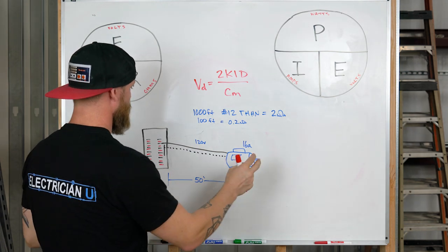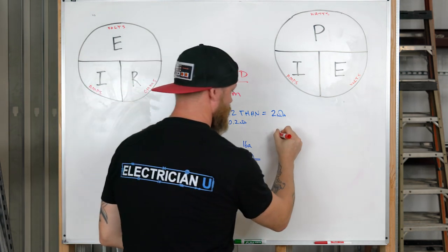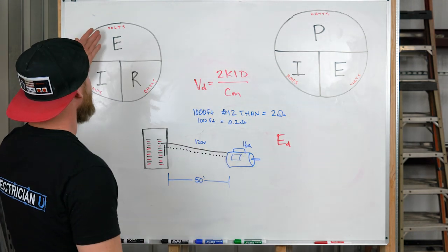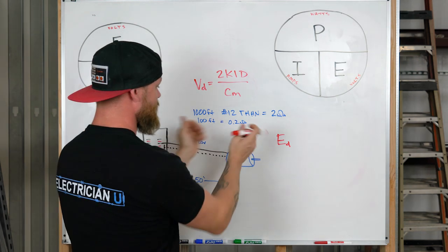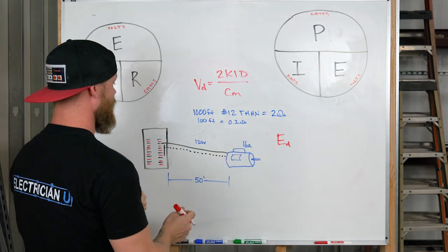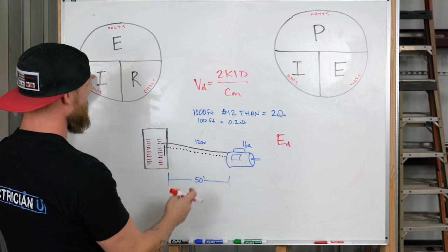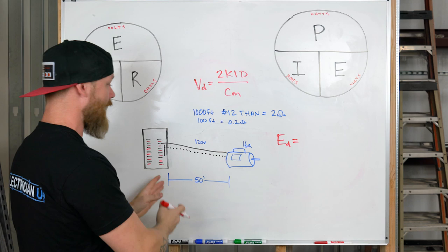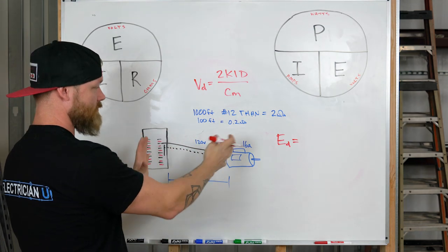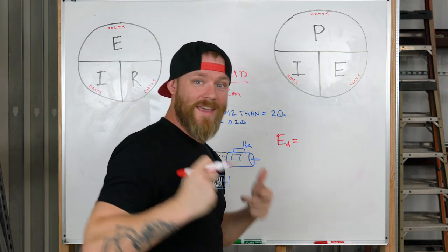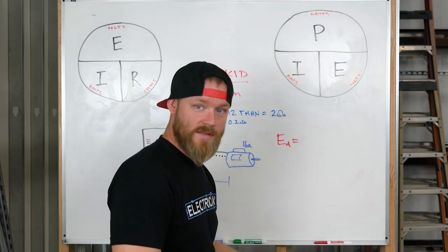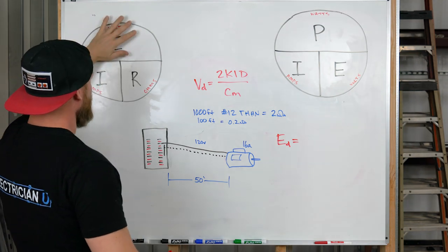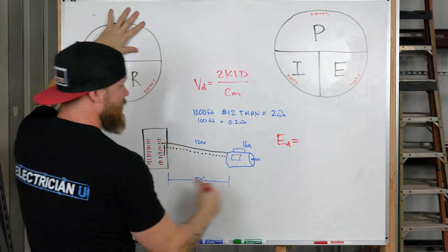we're trying to solve for voltage drop. So ED, voltage drop. A lot of people would think, okay, well, I see voltage, I see amperage, so that means I can plug my voltage and my amperage in, but that doesn't help you because what you're trying to solve for is voltage drop, not the voltage of this system. We're trying to figure out, once we kick this motor on, how many volts this circuit is going to drop over the whole distance? So we would take I times R.